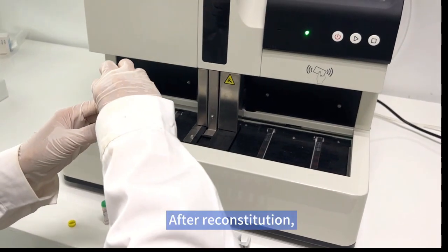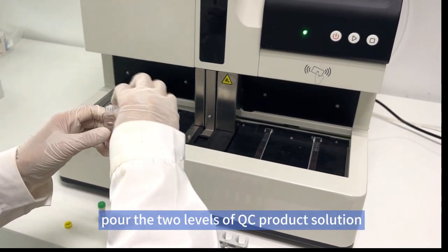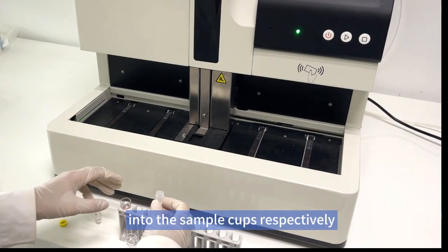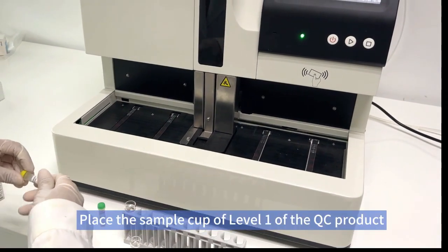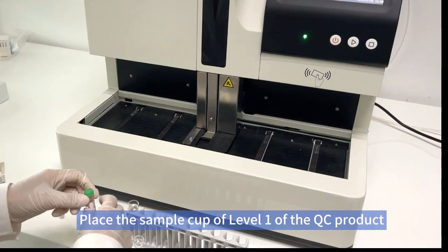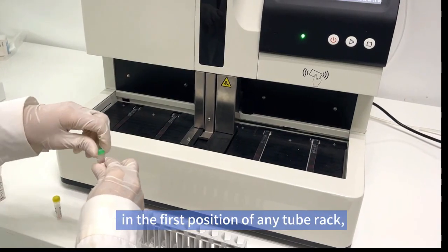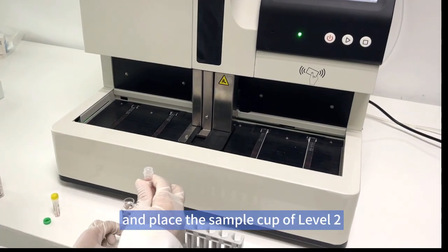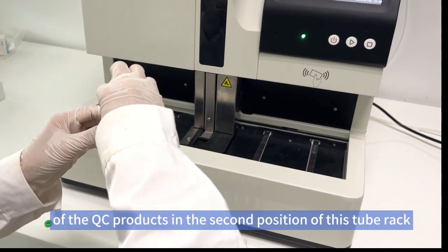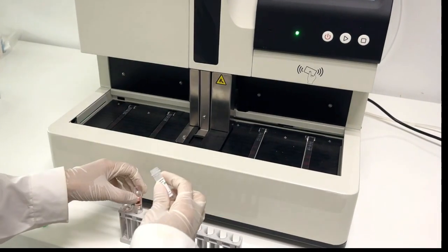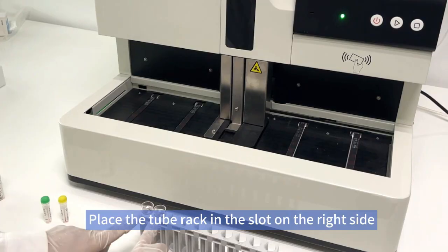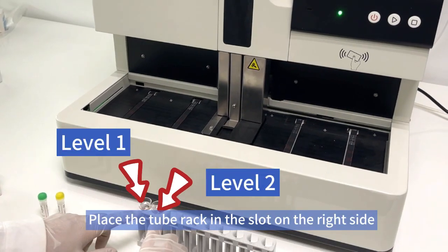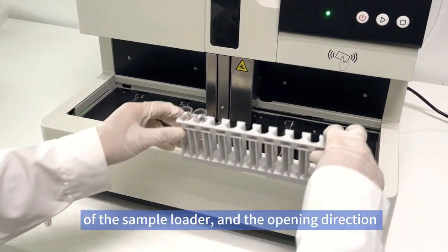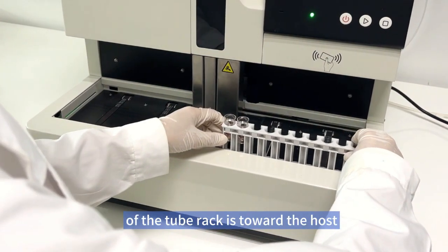After reconstitution, pour the 2 levels of QC product solution into the sample cups respectively. Place the sample cup of level 1 of the QC product in the first position of any tube rack, and place the sample cup of level 2 of the QC products in the second position of this tube rack. Place the tube rack in the slot on the right side of the sample loader, and the opening direction of the tube rack is toward the host.